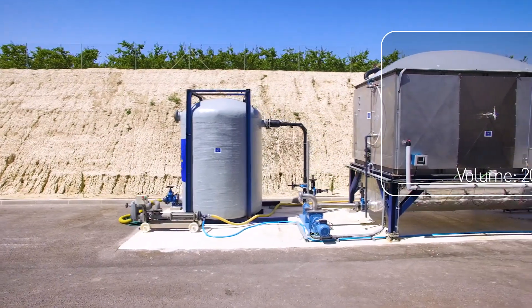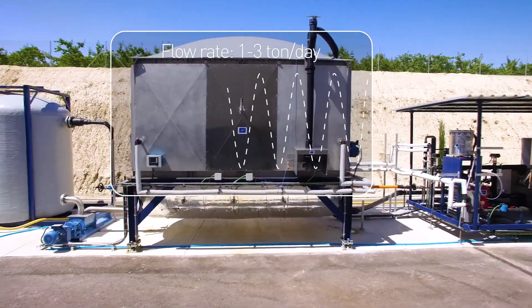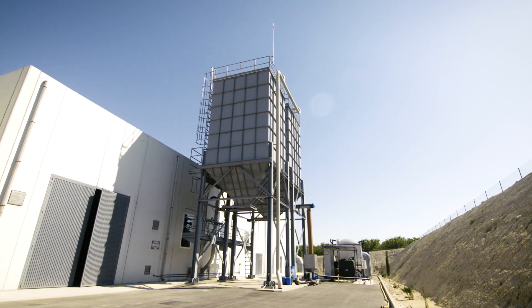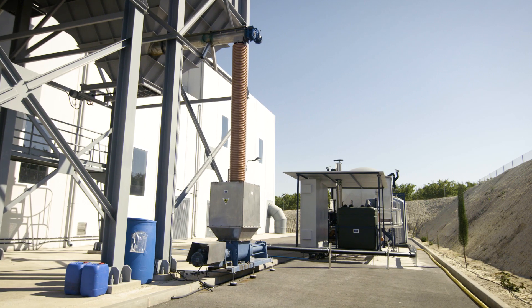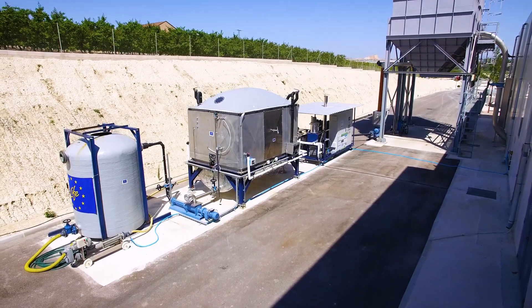The design proposed at pre-industrial scale is based on a cylindrical reactor of 20 cubic meters that can treat up to 3 tons per day of sewage sludge. The system works as a dry anaerobic digestion, with the solids' concentration on the inlet sludge being around 15 to 20 percent.